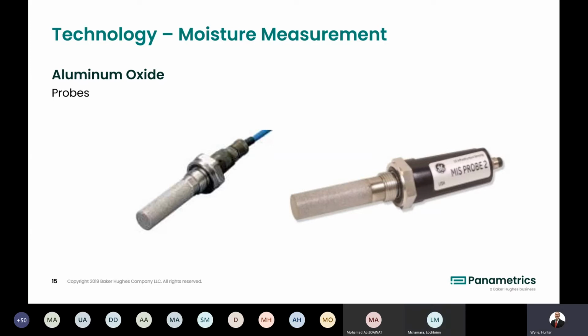And a follow-up question to that is, what other potential technologies or options would there be for lower than that LDL? Well, aluminium oxide would be the sensor that we would use for those applications that are below 2 ppm. There are other technologies that we don't support, like quartz crystal, but that can be a lot more expensive per measurement point, and requires recalibration in the field, re-zeroing of references. So for us, we would primarily focus on the aluminium oxide sensor.